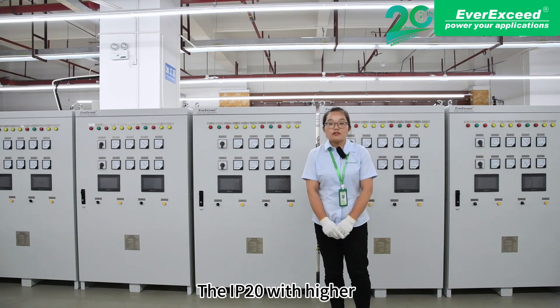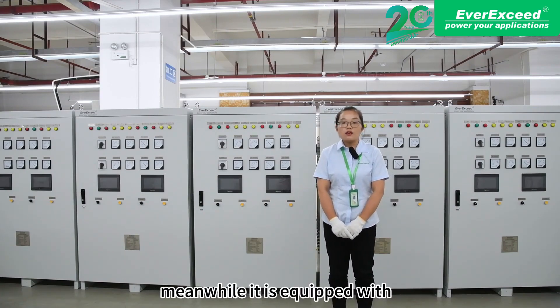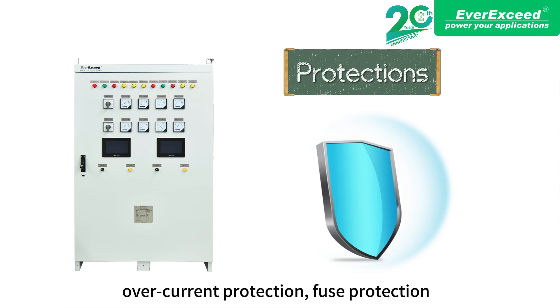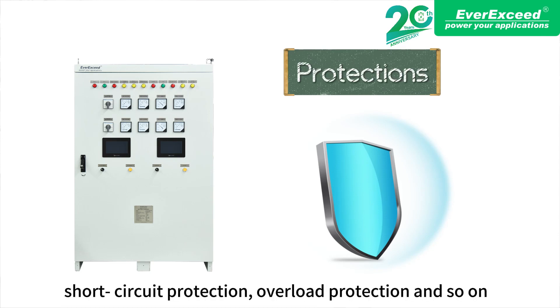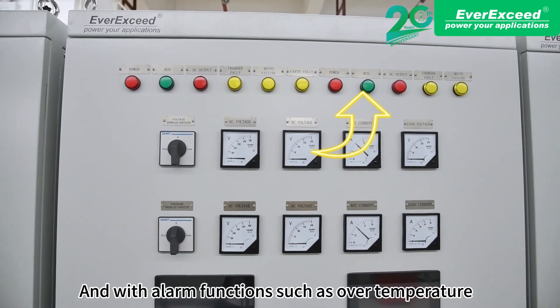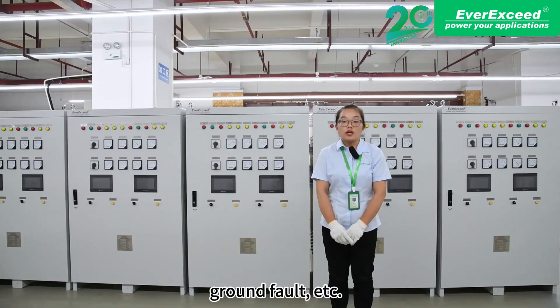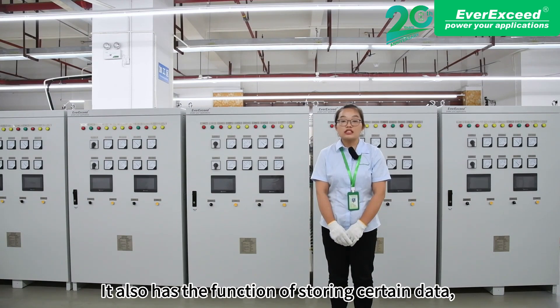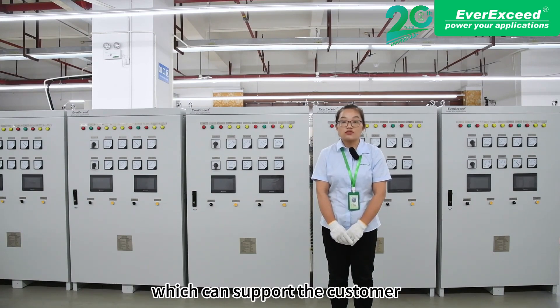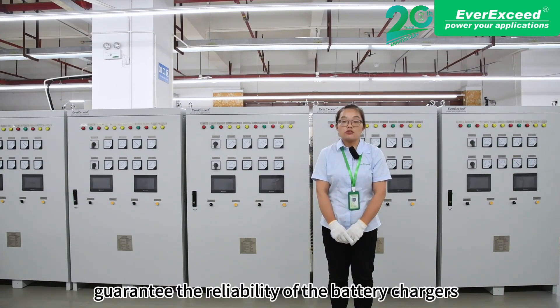The IP20 rating offers higher operation resistance and security. Meanwhile, it is equipped with overcurrent protection, fuse protection, short-circuit protection, overload protection, and more. It also has alarm functions such as overload temperature, mains failure alarm, charger failure alarm, and ground fault. It also has the function of storing certain data, which allows customers to check alarm events and download them at any time. All these features guarantee the reliability of the battery chargers.